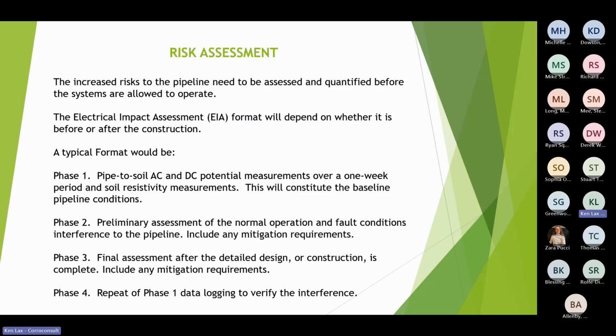And that constitutes the baseline pipeline conditions, so that when the development proceeds and they power up the new system, we'll be able to compare the electrical interference on the pipeline with what's been delivered after the system's in operation. And the reason we do this is to protect both the pipeline operator and the developer, because if you work on the theoretical example, say of 15 volts being acceptable as an AC interference before you start to pay any attention to mitigation, let's say you were already suffering from 12 volts on your pipeline, which is below the threshold, but the pipeline operator is monitoring it and has got it all in hand.